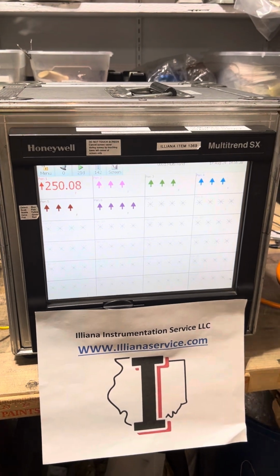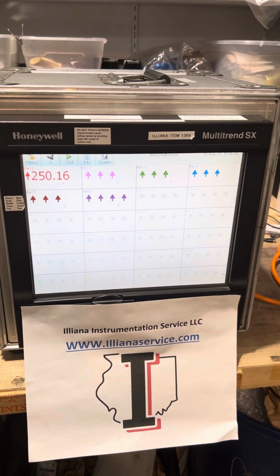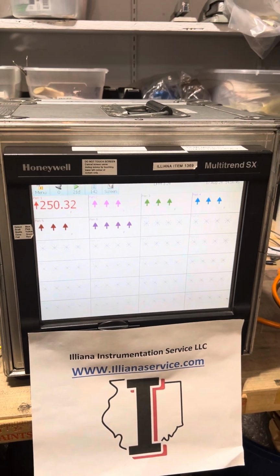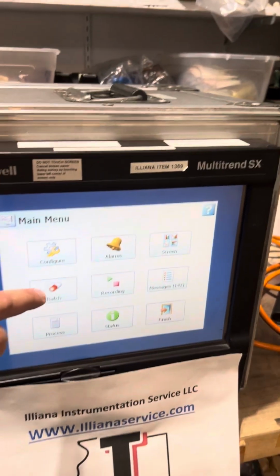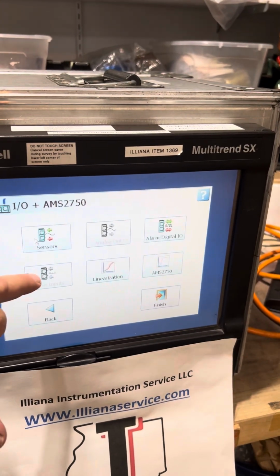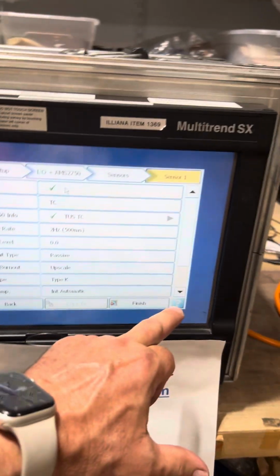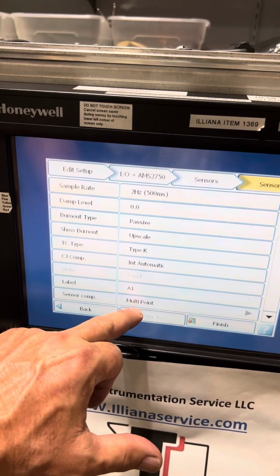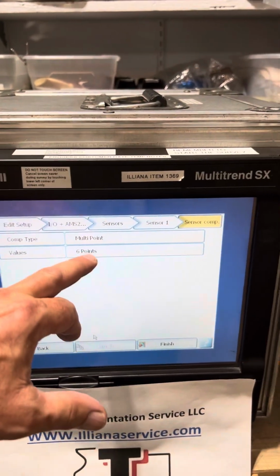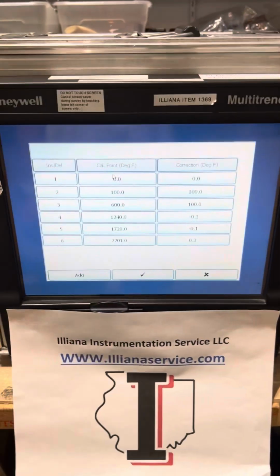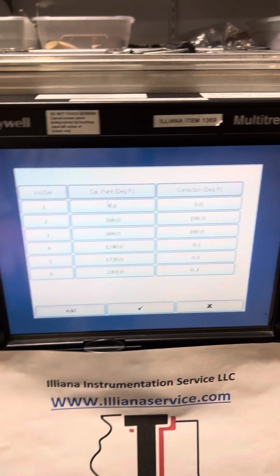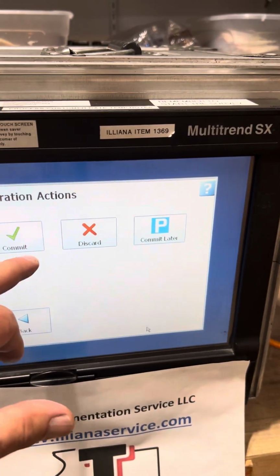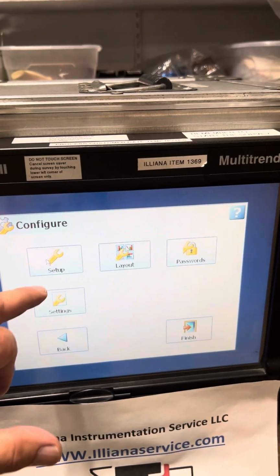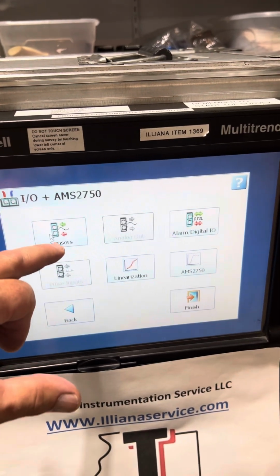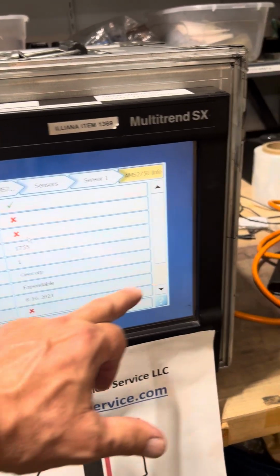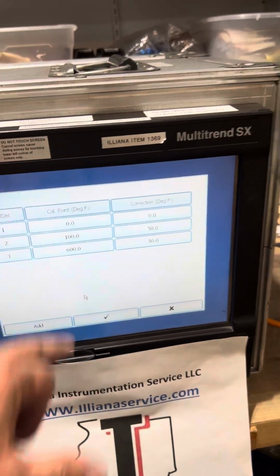So to summarize, there are two features in the recorder that allow you to make offsets to the readings. One of the features is designed to allow you to properly calibrate the recorder, and that is this one down here called Sensor Compensation Multi-point. The name's a little misleading, but it's this one where you build a table, and those are your 6 calibration points as required by AMS 2750. That is to correct the recorder, and the other one is to put in correction factors for your wire, and that one is put in here. It is called Cal Adjust, 3 points right in there.